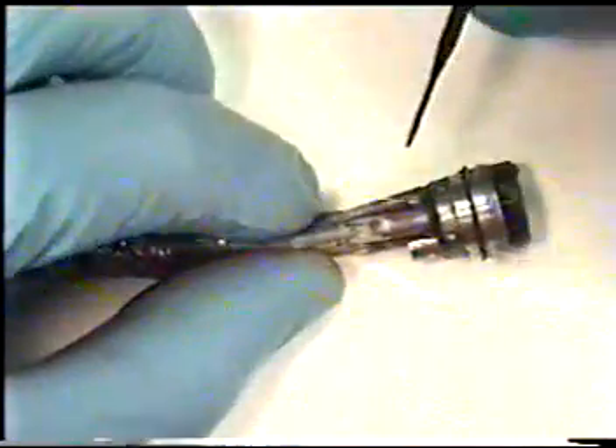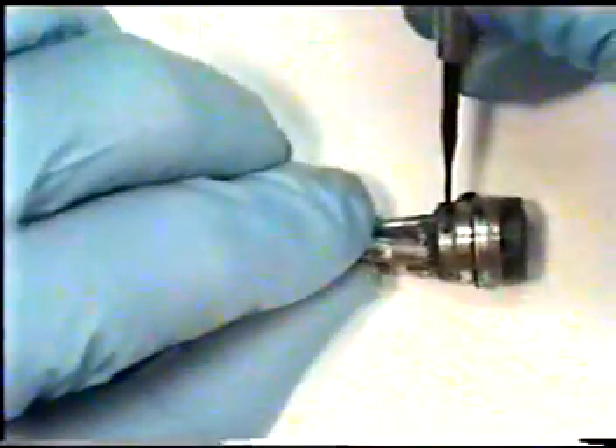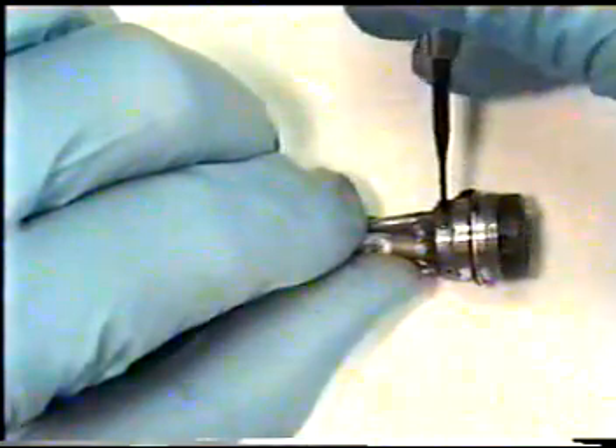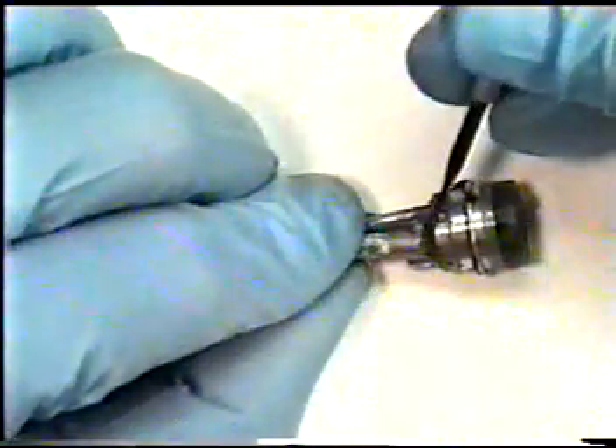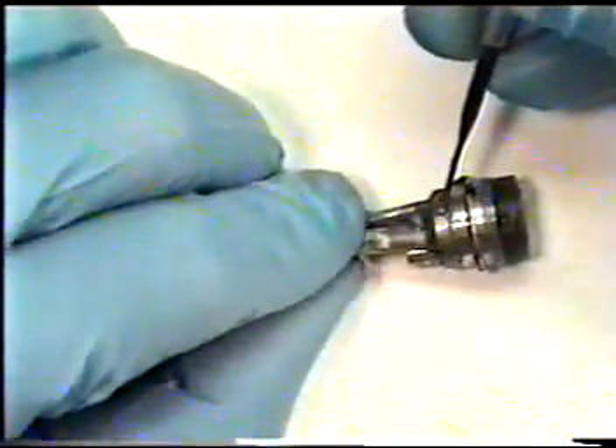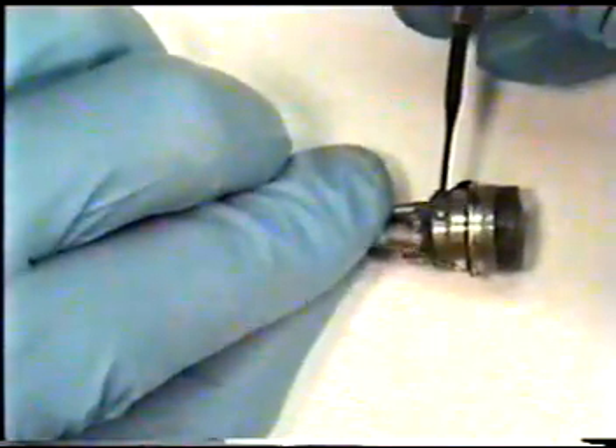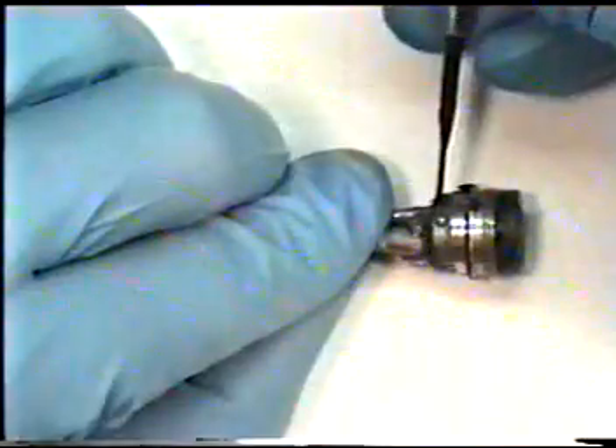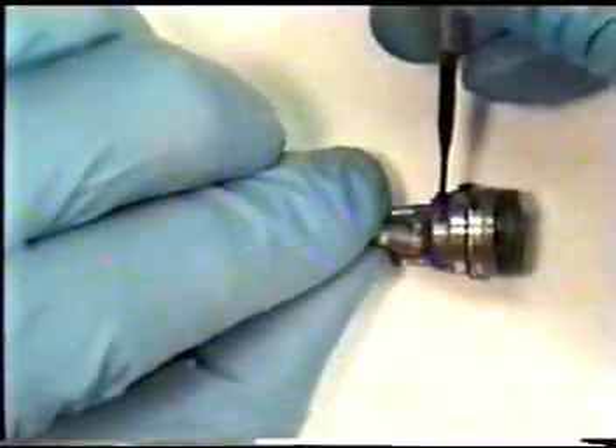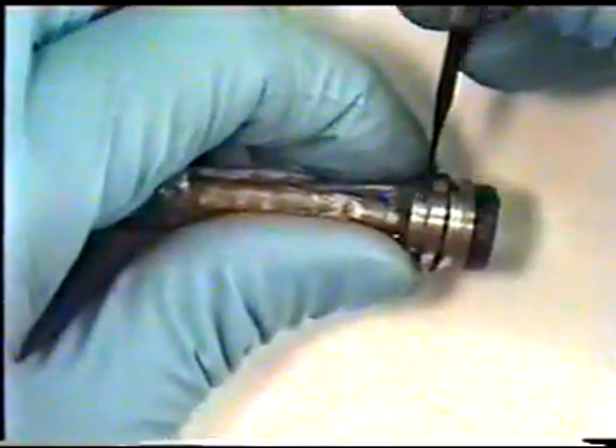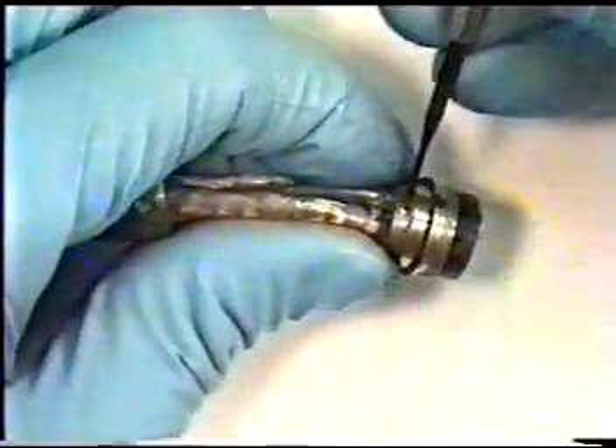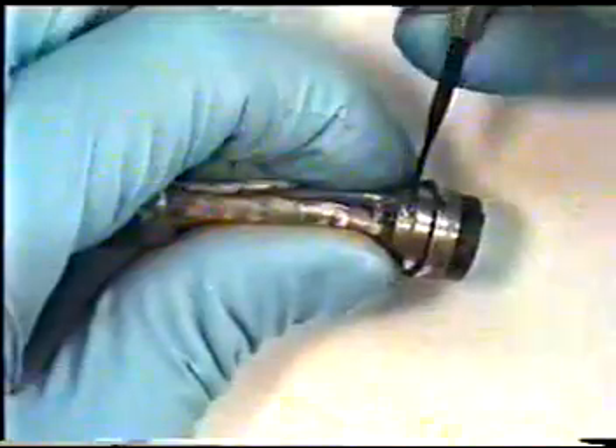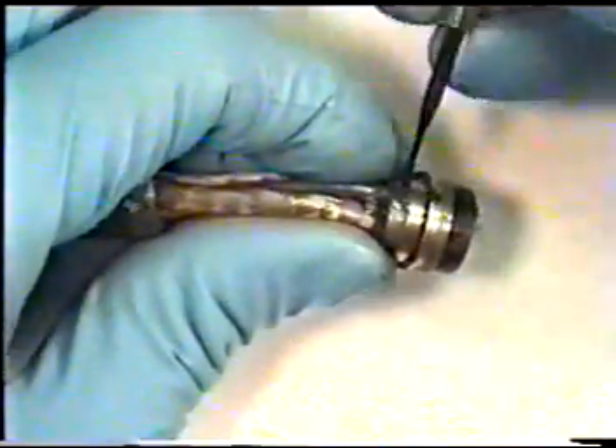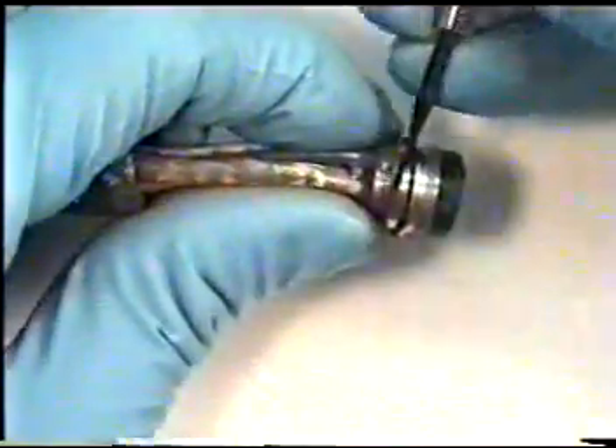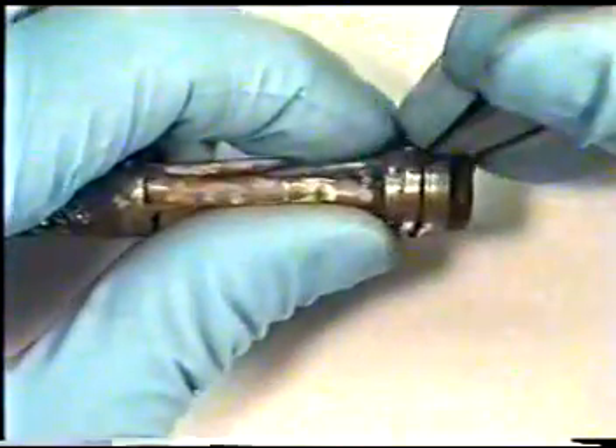Using a very small number 1 screwdriver, unscrew the locking set screws which point into your light guide illumination bundles. Usually the set screw is at a 90-degree angle on the distal end assembly, pointing towards your light guide bundle. Unscrew set screw counterclockwise. Remove set screw completely from the hole.